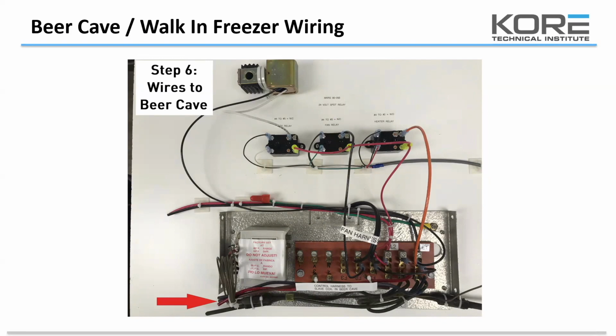You will also find that we're taking a wire from H2. In this particular picture, it's a red wire. That will go to H2 in the slave coil to complete the circuit for the heaters. And in this picture, we also have a brown wire that is attached to F2, which will also take power to the fans, and that will allow us to run the fan. So everything is being run from the master coil.